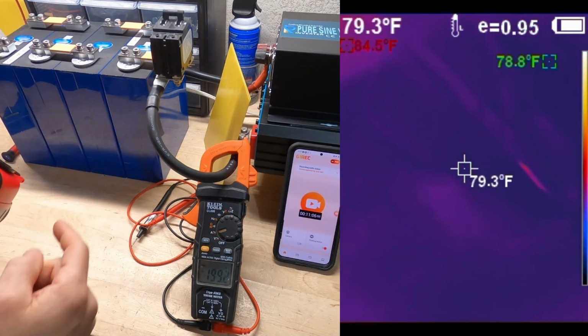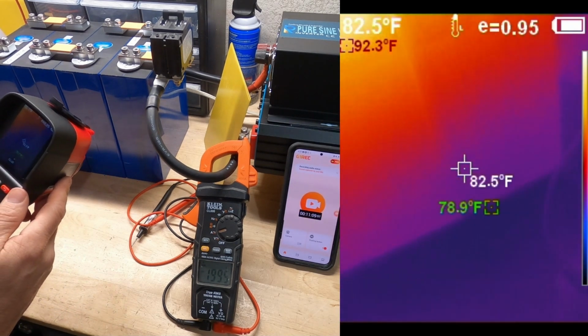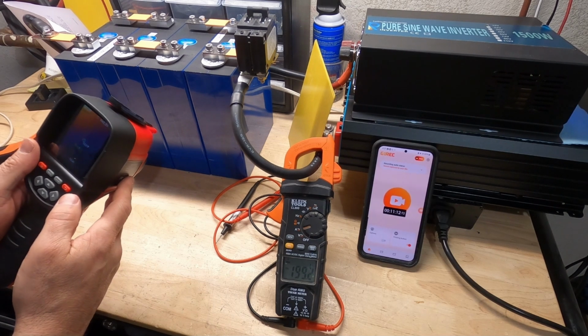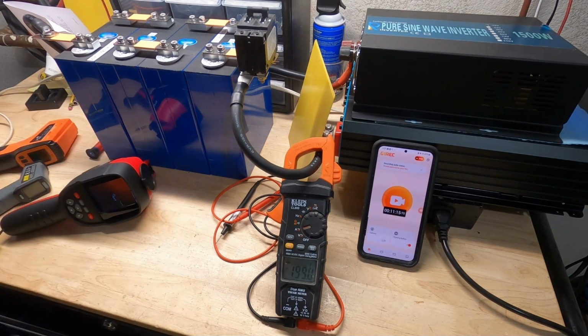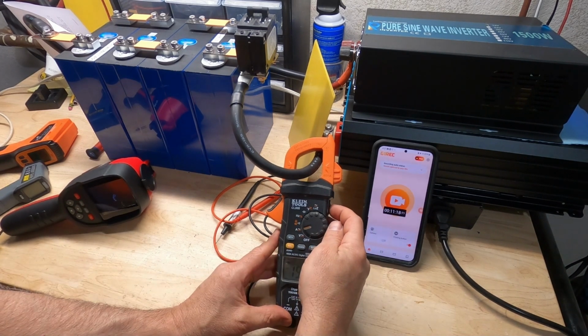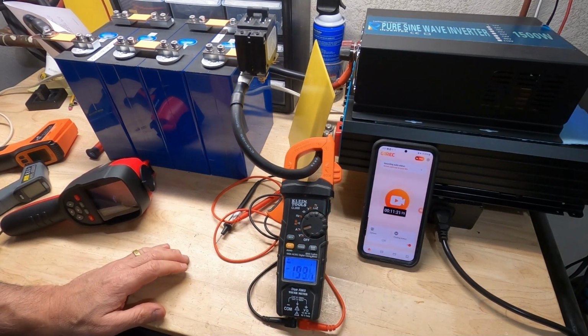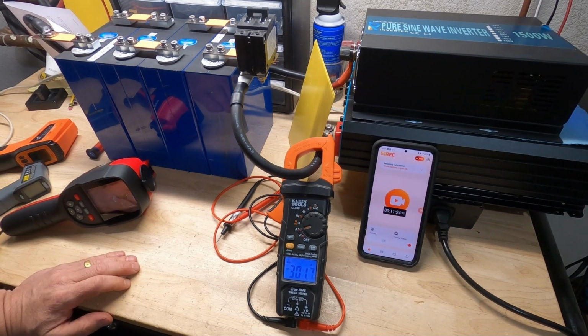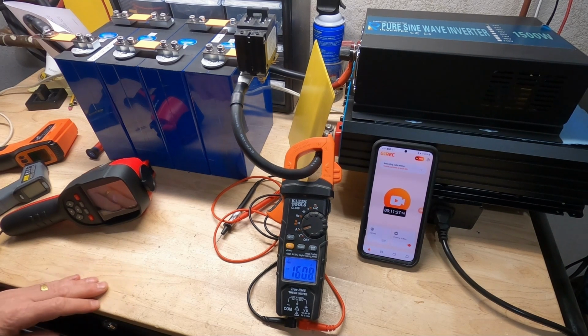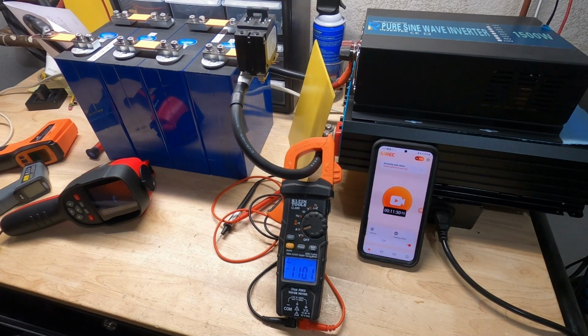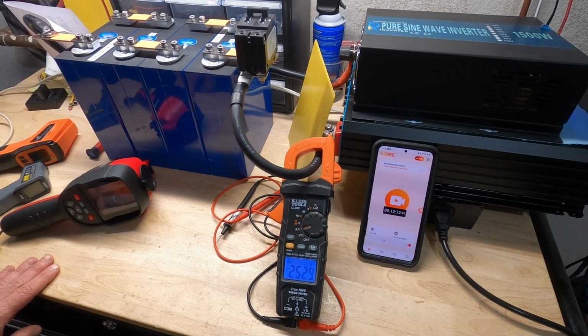Let's go ahead and boost it up, and we'll make sure the breaker trips at or around 220 amps. We're going to boost everything up. Here we go. 300 amps. Oh, the inverter cut out. Inverter couldn't do it. Let's reset. Okay, here we go. There, 250 amps. It's got a trip rating of 275 amps.